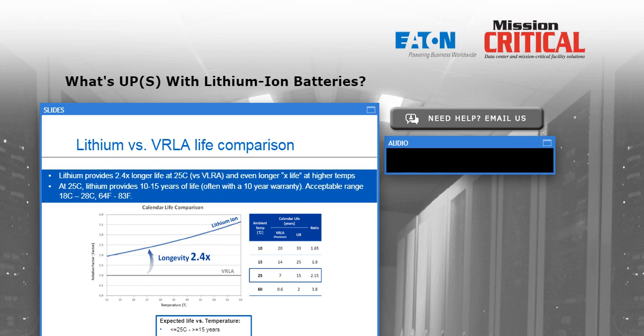At 40 degrees C, about 104 Fahrenheit, remember the VRLA battery has a relative factor of 1.0. So is a valve-regulated lead-acid battery a 5-year battery at 40 degrees C? No, it is not - it's about a 2-year battery at that temperature, and lithium is 2 to 3 times more than that, which is good, but that's not 10 years. That's 2 years times 3, or 6 years of lifetime. So if I choose to operate a typical lithium solution in very hot temperatures on an annual average basis, I'm not going to get the full 10-year expected life.